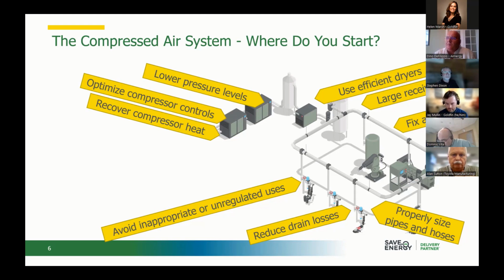Okay, no, definitely. There are optimizers that will take a look at the VFD and switch to fixed speed if it hits a certain capacity or KW, to be honest with you. Yeah, it's interesting - years ago we did that; we had some smart techs in a plant, and they actually used just a PLC controller to do that. They had some air monitoring and pressure and so on, so they were able to do it with a generic PLC system and a smart programmer. But maybe it is something you want to use an optimizer for.